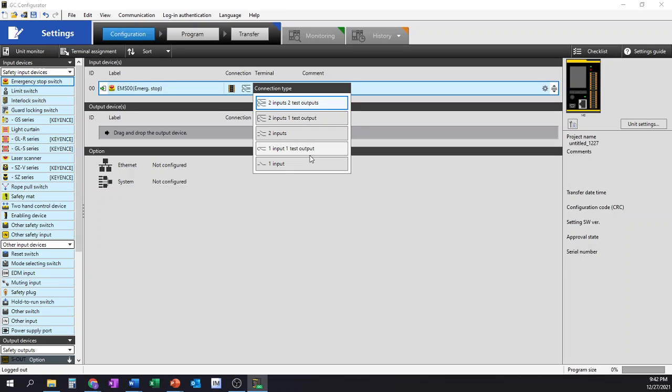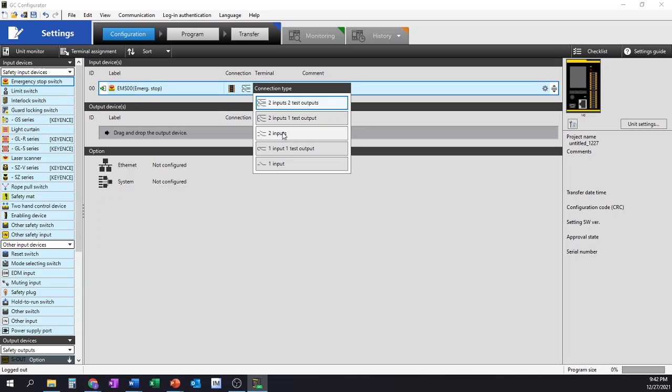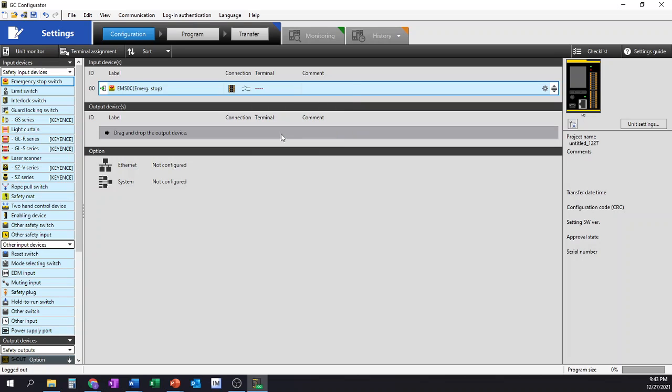You'll have to run your risk assessment to better understand what that requirement is going to be, but nevertheless it's still there for us to use. You also have the two inputs, one test output, so rather than running two outputs to power that, you're going to run one test output, one power out to your button, then from your button, two inputs in return back. Still meets your safety criteria, but run your risk assessment, determine your requirements, and from there you would go into that. Personally, I like to run everything on a dedicated 24 volt DC power instead of running my outputs, so I would go with the two inputs. But that's just me. You can do it however you see fit or whatever your standard for your company might be.